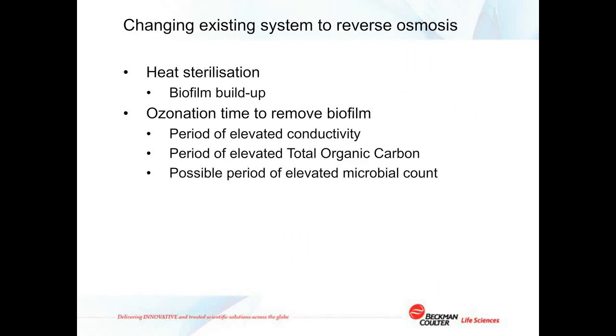If a water for injection system is quite old, there's a very real possibility of biofilm buildup. Microbes can live in the biofilm in an oligotrophic state without being detected. A common error when retrofitting an ozone sanitized reverse osmosis plant to such a water system is not allowing for a suitable time period to allow the water system to come back under control.